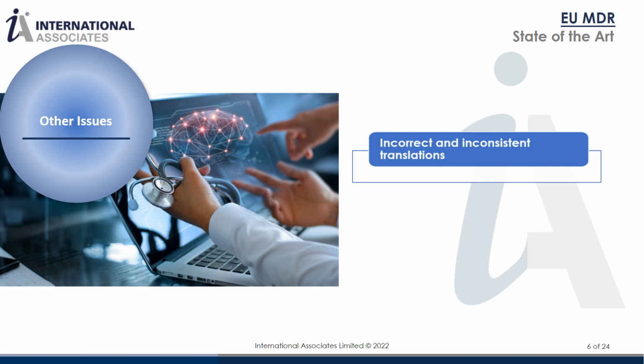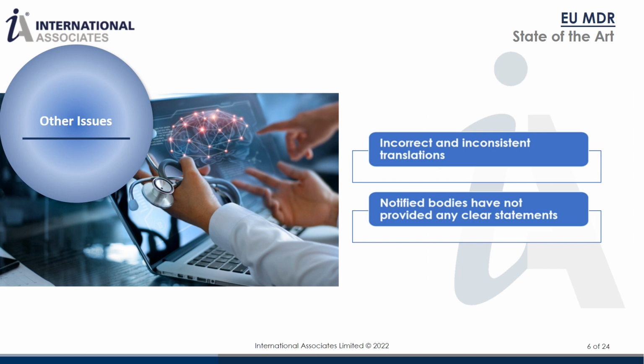Even when expressly asked, notified bodies are reluctant or are even not allowed to make a clear statement on whether manufacturers should reference standards when having their devices authorized, and, if so, which standards and versions they should reference. Such as standards harmonized under the directives, standards planned for harmonization under the MDR or IVDR, or the latest version of the standards.